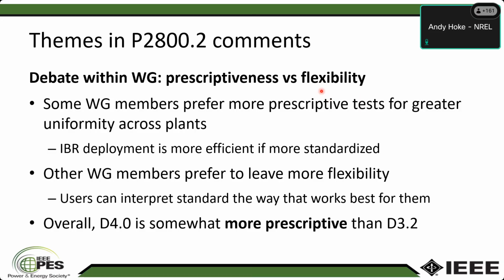Some of the working group members would prefer to leave most of the tests fairly general or fairly vague even, because it gives you the flexibility to deal with the fact that not every plant is the same, not every system you're connecting to is the same, and you need some flexibility to be able to tweak the procedures to fit the specific application. So that's the balance we've been trying to strike the whole time, and there's some pretty strong opinions on both sides. Overall, when we went from the previous draft 3.2 to the draft that will be released like tomorrow probably, draft 4, it's a little bit more prescriptive. Some of the tests have a little bit more detail, but it's still pretty general and flexible.